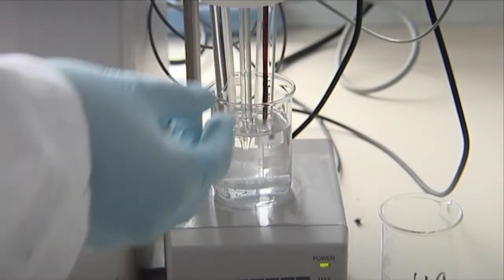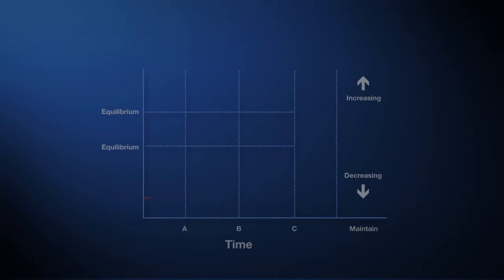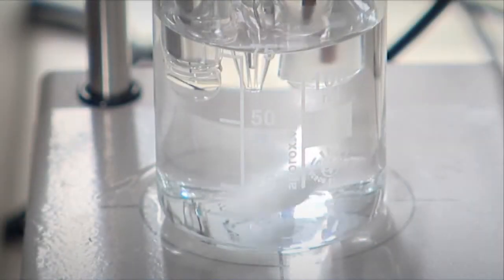The second test we run is the acidity, and this is a measurement of the oxidation of the oil. It generally remains stable over the lifetime of the oil, but as the oil starts to age and degrade, you'll see an increase in the acidity measurement.